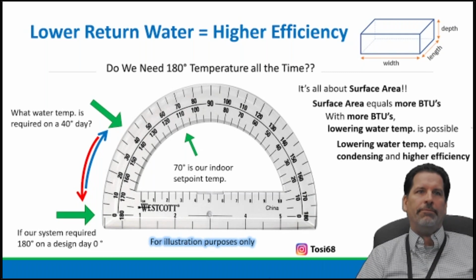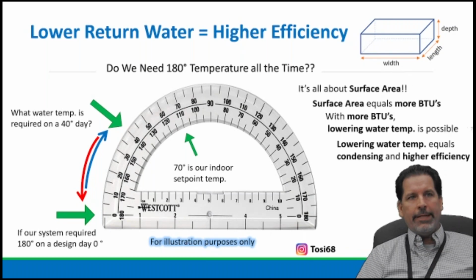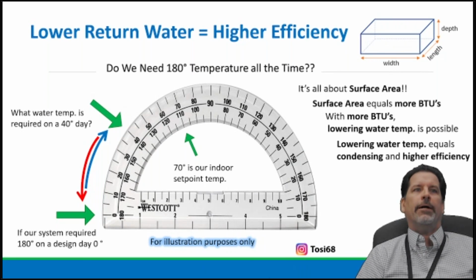I used to hand out these little 50-cent protractors. All the way down to the lower left corner, if you imagine, if it's a 0-degree day outside, that's why we need 180-degree water. So think about that. Why is it that we have 180 and only 180 all the time? That's the worst day of the heating season, that coldest night of winter. If it's a 0-degree night, that's when you need 180.